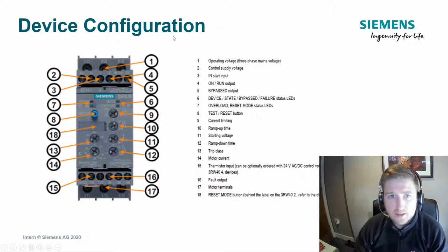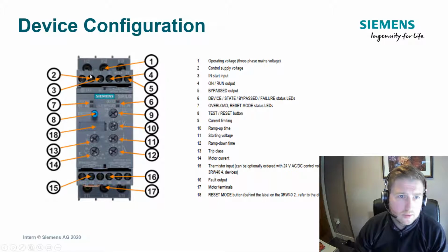So we'll move on to the next slide now, and this just gives you an overview of the actual device's configuration. This tab here, labeled number 1, is where your mains infeed comes in, and tab 17 here is the output to the motor terminals. In a similar fashion to the 3RW30, you've got number 2, labeled A1 and A2. That's for the control supply voltage. You need power to your control circuit, and you also need power to this terminal here, number 3, which is labeled terminal 1. So you need the control circuit to be accessed, and you also need terminal 1 to be initiated to gain a start sequence of this particular soft starter.